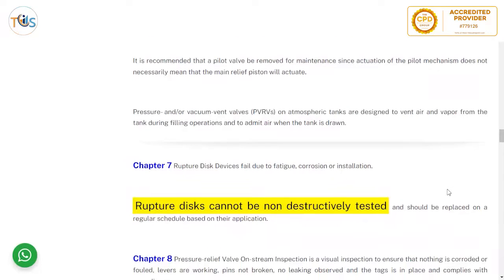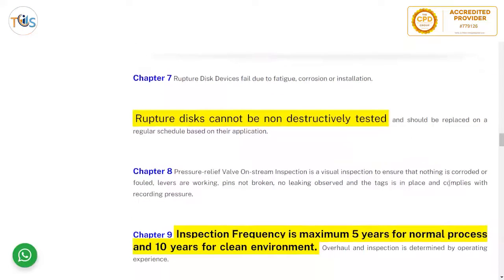It is recommended that the pilot valve be removed for maintenance, since actuation of the pilot mechanism does not necessarily mean that the main relief piston will actuate. Pressure and/or vacuum vent valves on atmospheric tanks are designed to vent air and vapor from the tank during filling operations and to admit air when the tank is emptied. Rupture disc devices fail due to fatigue, corrosion, or installation errors; rupture discs cannot be non-destructively tested and should be replaced on a regular schedule based on their application.